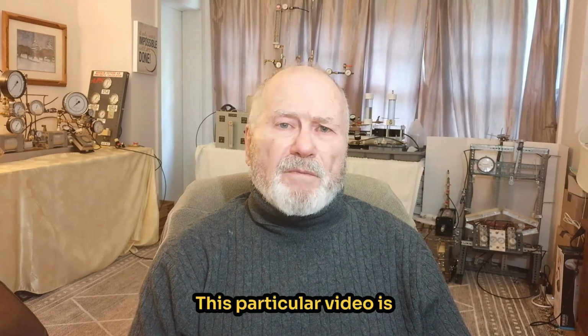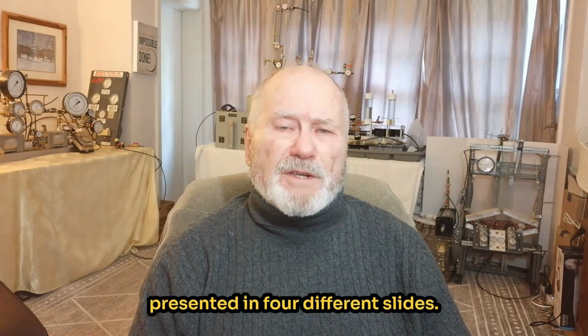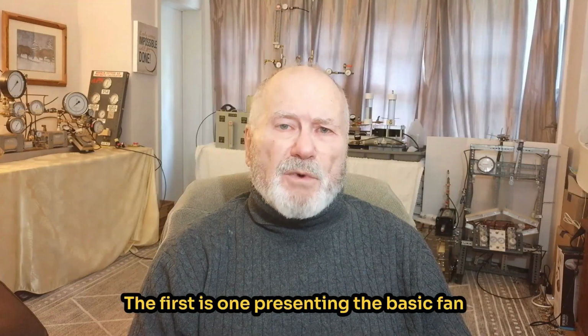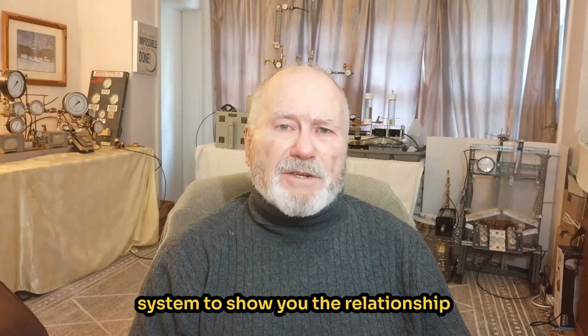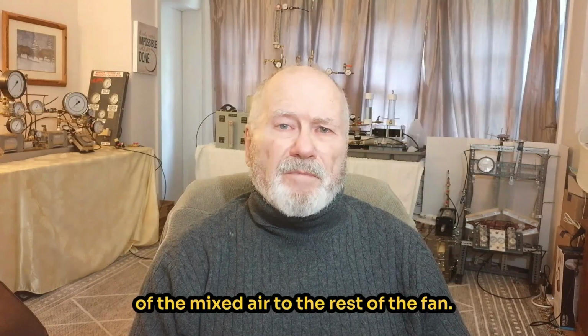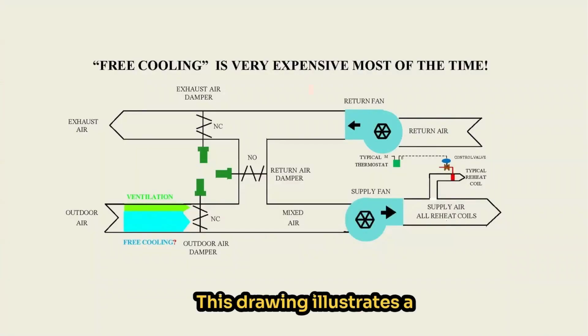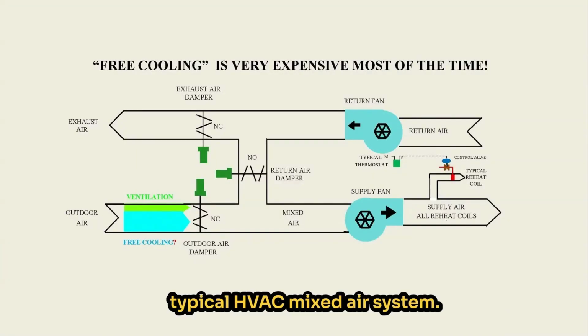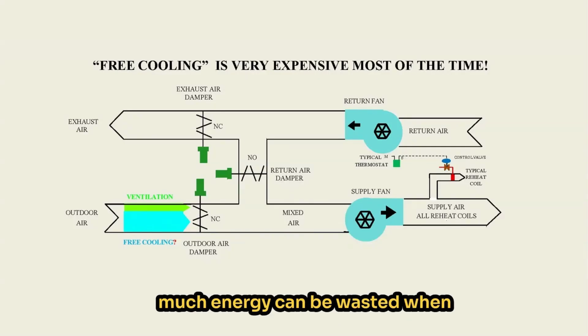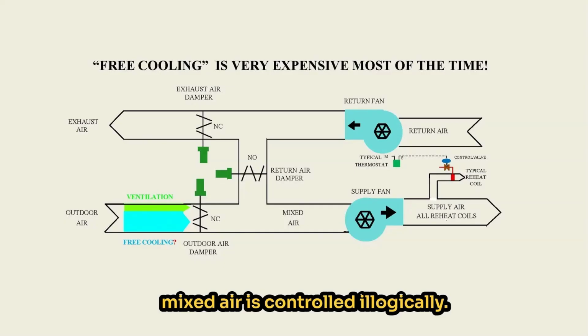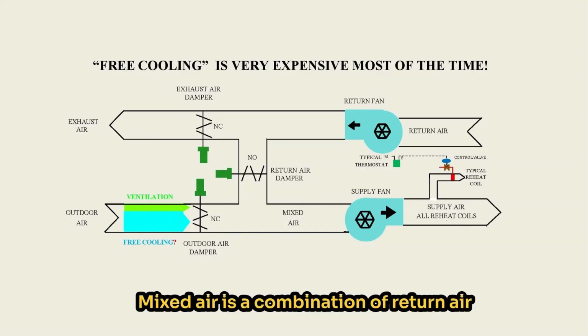This particular video is presented in 4 different slides. The first is one presenting the basic fan system to show you the relationship of the mixed air to the rest of the fan. This drawing illustrates a typical HVAC mixed air system. It is essential for everyone in our industry to understand how much energy can be wasted when mixed air is controlled illogically. Mixed air is a combination of return air from the building and fresh outdoor air.